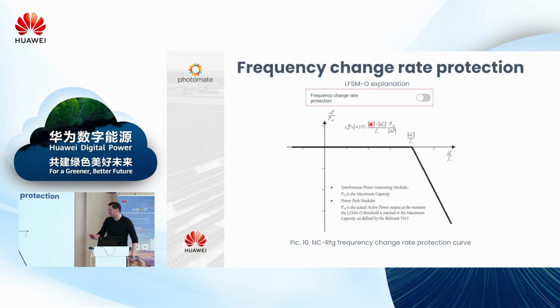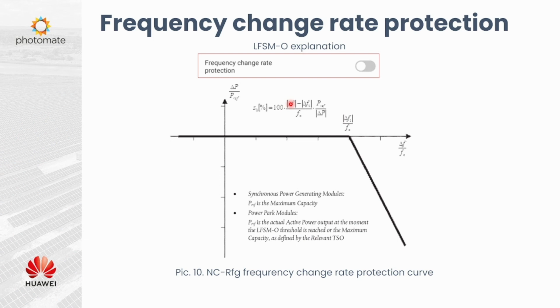Okay, very fast about this, just to understand how it works. Frequency change rate protection, it's not very important in residential, but super important in industrial. If you just enable it, the inverter will behave like this. So if there are rapid changes of frequency, it will just reduce active power. This is how it must behave regarding some standards. So just for your information, do not enable it if you don't need it, or somebody else will ask for it.